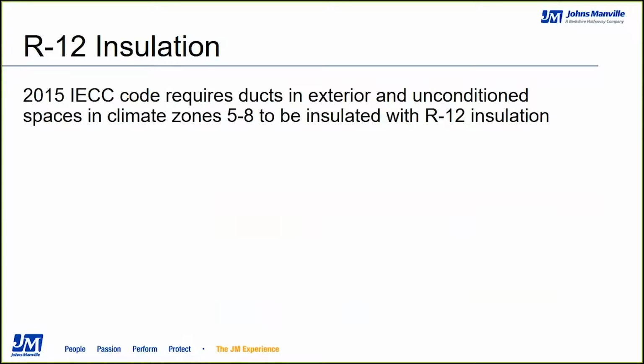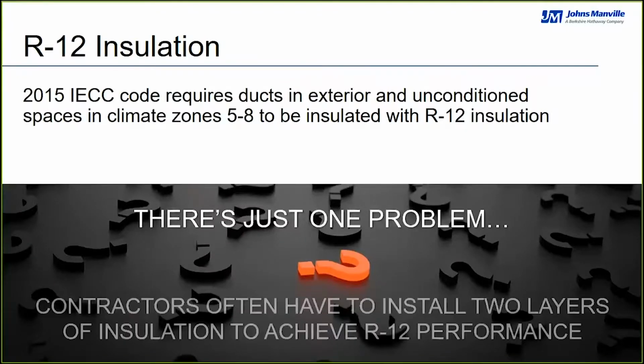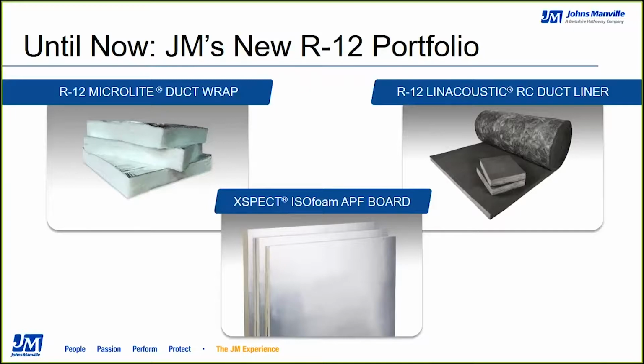In the most recently adopted 2015 IECC, which is now being adopted at state levels, the code requires ductwork in exterior and unconditioned spaces in climate zones 5 and above to be insulated with R12 insulation. However, contractors have often had to install 2 or more layers of insulation to achieve R12 performance. Until now. JM has recently added to the product portfolio R12 Microlite duct wrap, measuring 4.4 or 4 2/5 inches thick, R12 Linacoustic RC duct liner with a 3-inch thickness, and Xspect Isofoam APF board in a 2-inch thickness achieving R13.